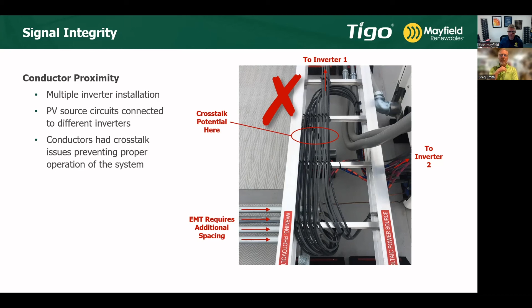Right where that arrow is for inverter 1, you can also see those conductors cross right under each other—there's a cross point there, so the whole cable tray might not have been accessible for them to move around. But nonetheless, these are things to be considered during the installation process as you're going through it.